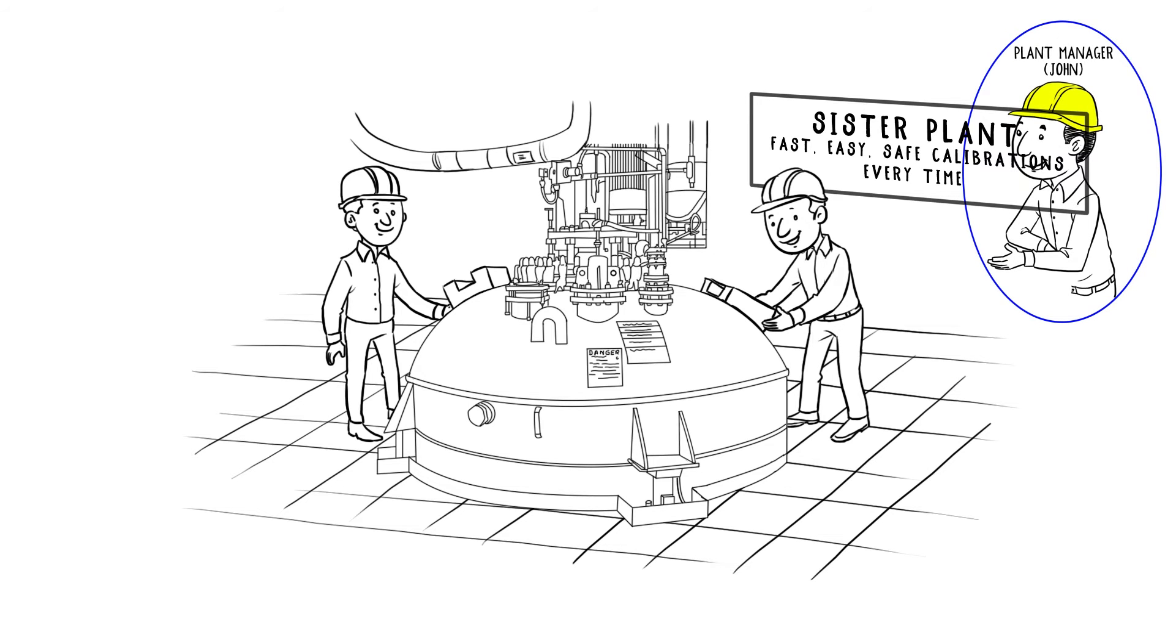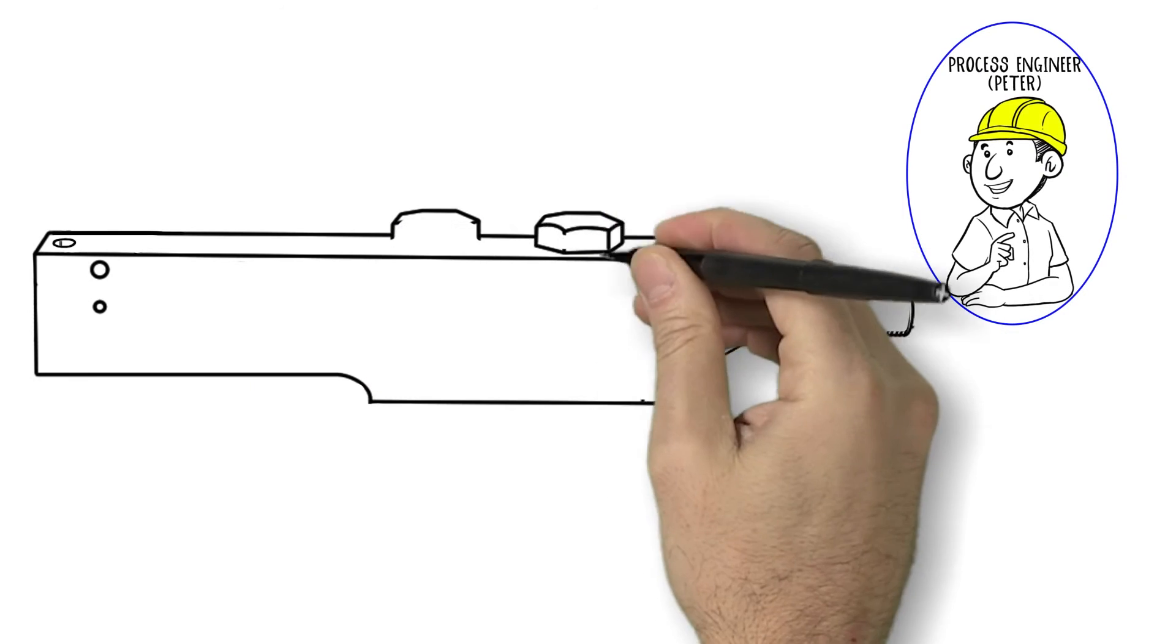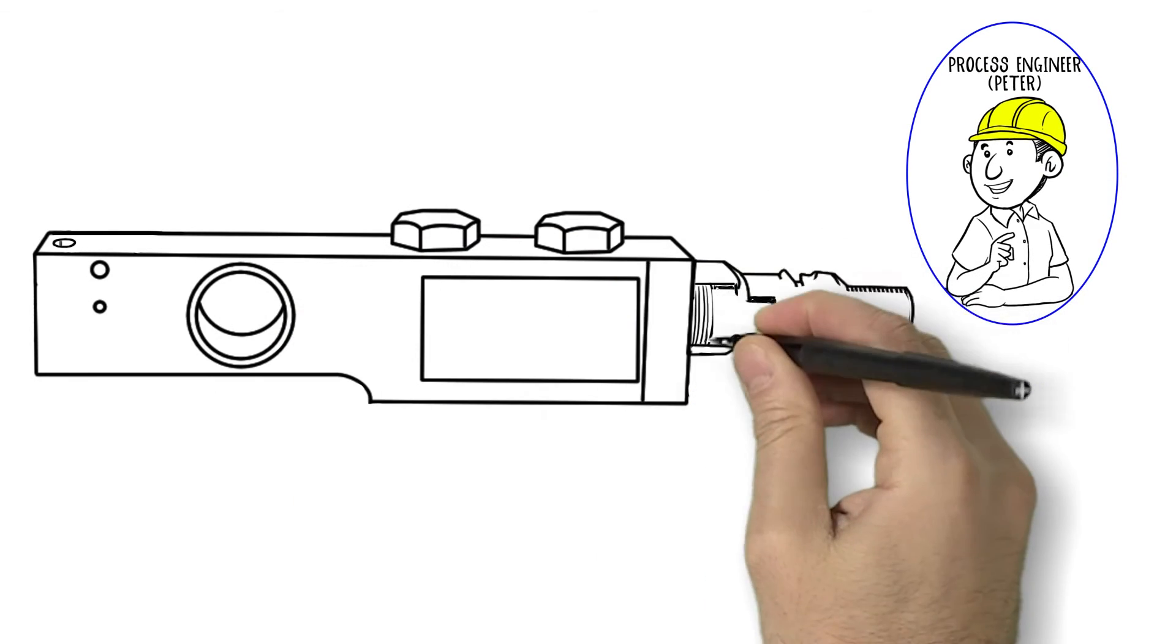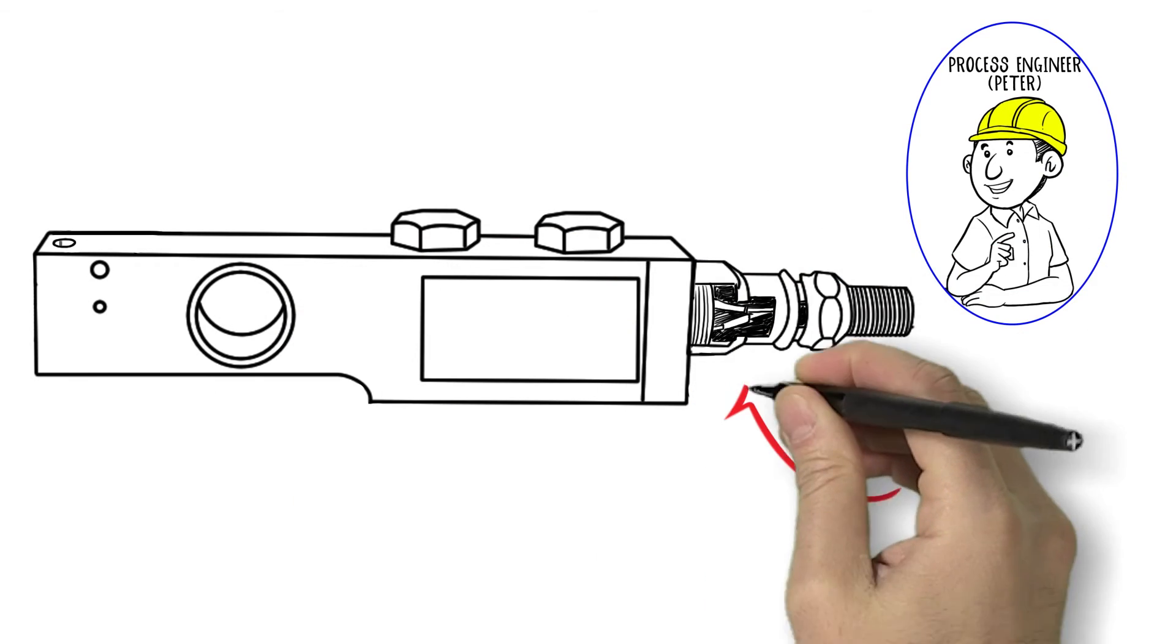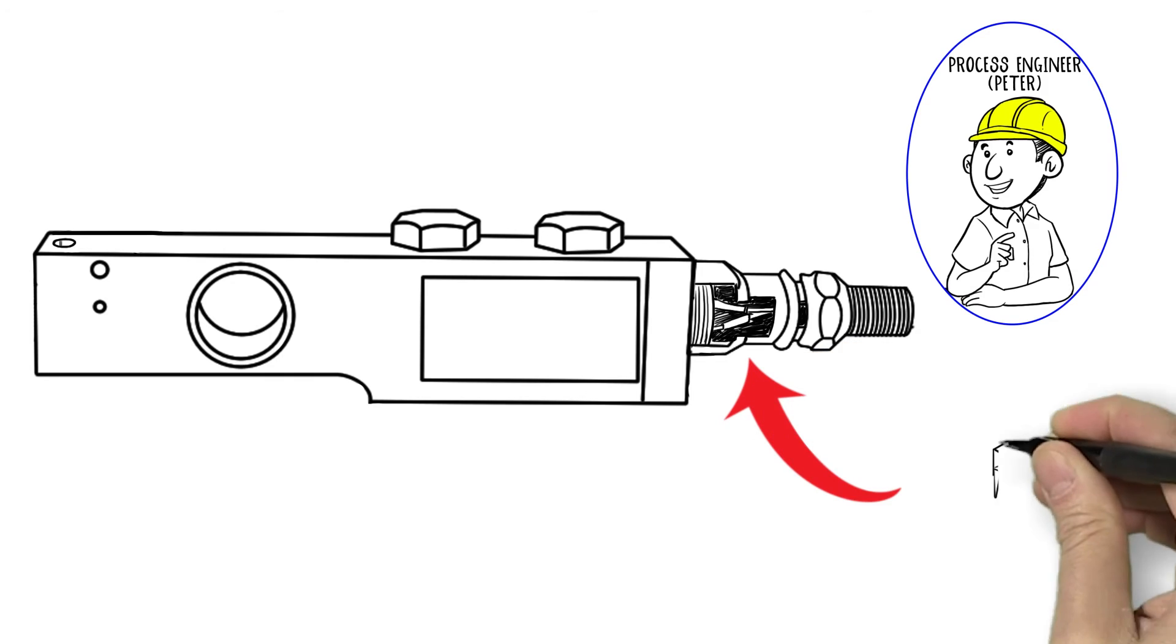How can Hardy scales cut calibration time in half? Hardy load cells are pre-calibrated. They store unique calibration data on each load cell, so we don't need to load a single test weight to calibrate the scales. It's already done. All we have to do is validate Hardy's calibration with a small test weight, typically about one-eighth of the test weight normally required.